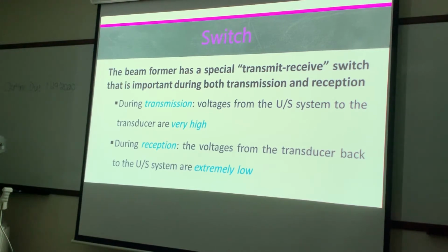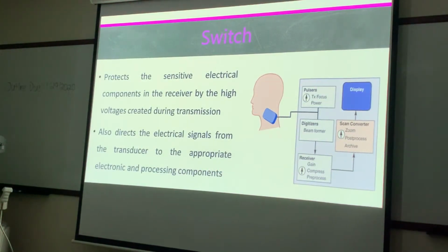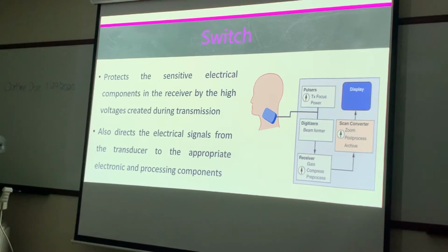The switch protects the voltages from the ultrasound system to the transducer, because those voltages are so high. It's going to protect that transducer. So during transmission, the voltages from the ultrasound system to the transducer are very high. During reception, the voltage from the transducer back to the ultrasound system is extremely low. The switch protects the sensitive electrical components in the receiver from high voltages during transmission.